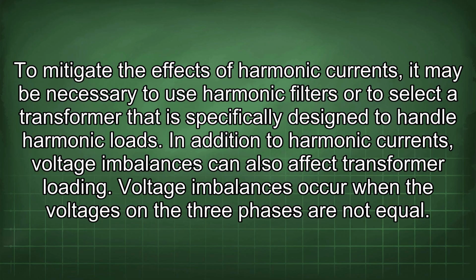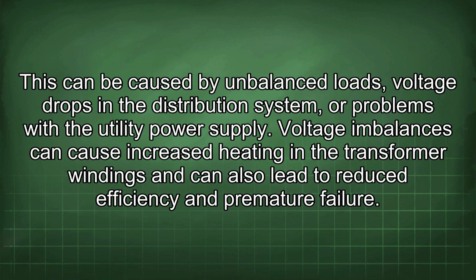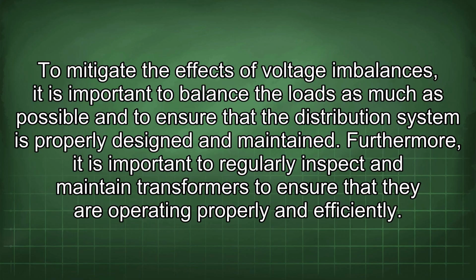In addition to harmonic currents, voltage imbalances can also affect transformer loading. Voltage imbalances occur when the voltages on the 3 phases are not equal. This can be caused by unbalanced loads, voltage drops in the distribution system, or problems with the utility power supply. Voltage imbalances can cause increased heating in the transformer windings and can also lead to reduced efficiency and premature failure. To mitigate the effects of voltage imbalances, it is important to balance the loads as much as possible and to ensure that the distribution system is properly designed and maintained.